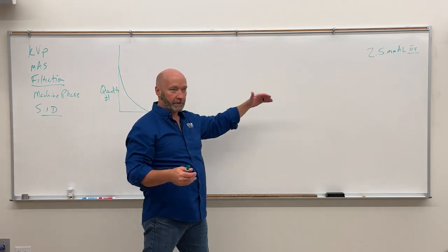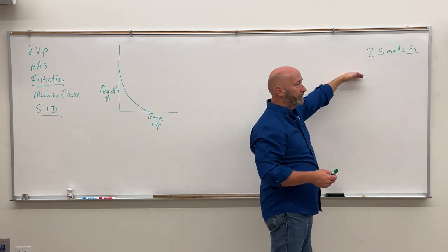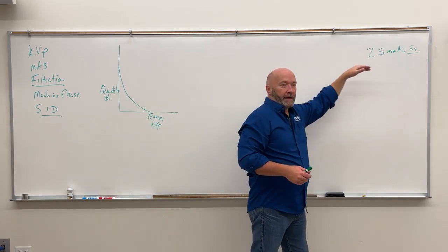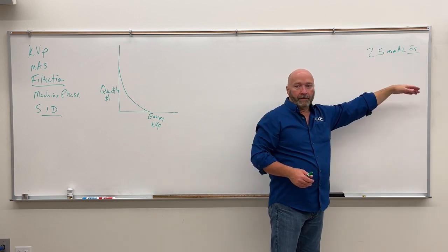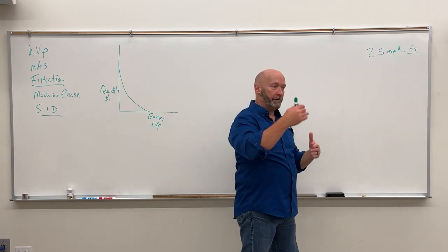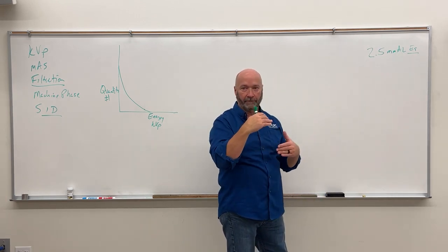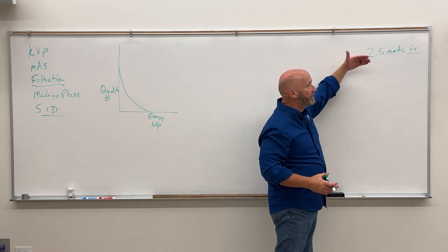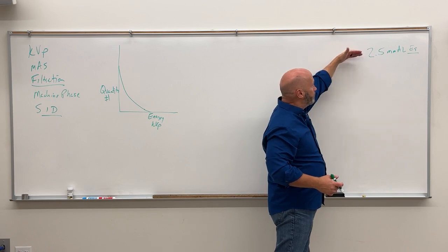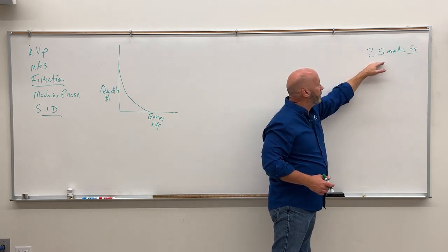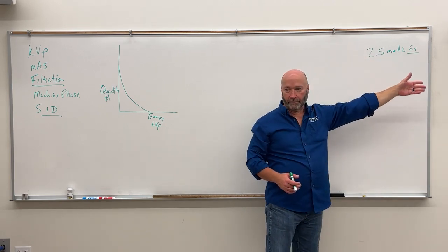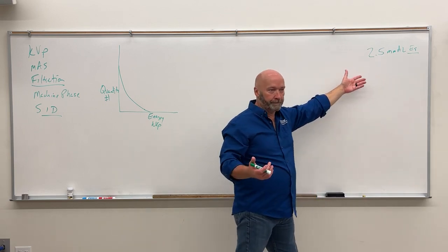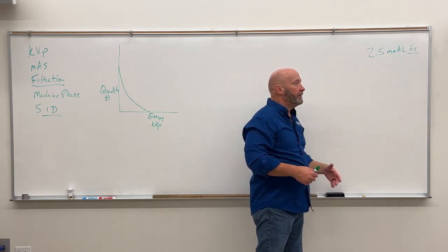The X-ray beam that you expose the patient to has to go through enough material that it would equal 2.5 millimeters of aluminum if you were just shooting directly from the target. So, if you had a metal envelope and it was thick enough metal and dense enough metal that it was the same as 2.5 millimeters of aluminum, you're golden, right? You're not gonna have that though.